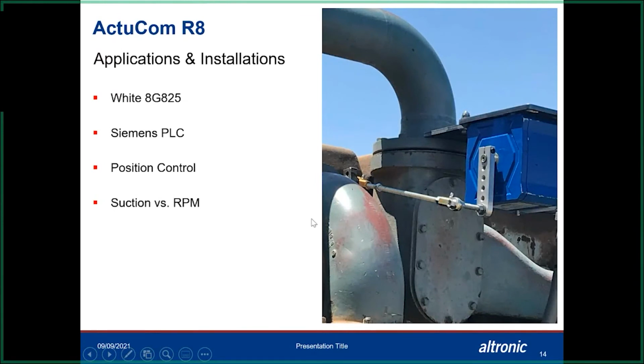This is one that is a straight manifold off of 8G also. I'm going pretty quick at this, so just stop me when you can. The Siemens PLC controls this one. So mainly with one of our customers, they do all their governor control through their PLC. But before they were using a Kinetro type valve sending the signal through I to P to it. So they found this real desirable to change. Plus we're doing some suction versus RPM on the control on that.